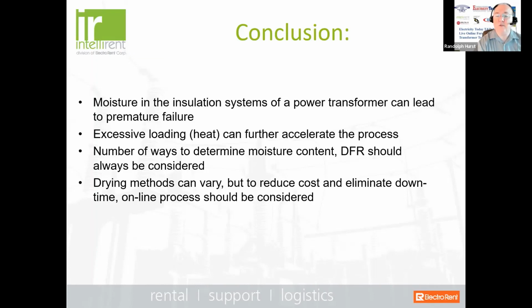Are there any statistics on how many transformers have failed due to moisture? Well, that's a really good question. Because, yes, I do have those statistics, and anybody's invited to send me an email, and I'll respond to that. But the problem is, if you have an insulation failure and it's gone too far, it's hard to determine exactly if moisture was a condition, depending on the extremity of the failure. If it was catastrophic, you've kind of passed that point of determining what happened in the insulation. But yes, I do have some statistics on that, and I'll be happy to send that to you.